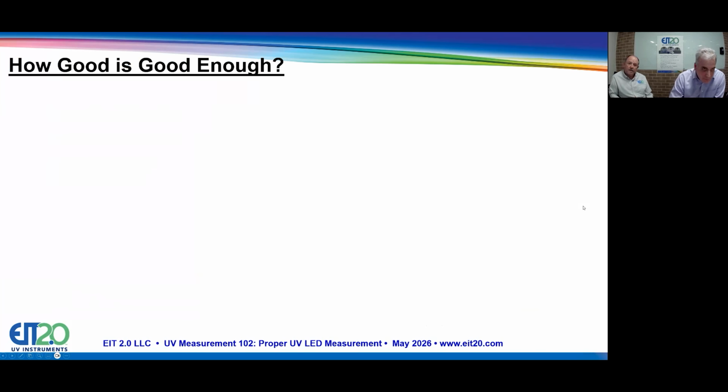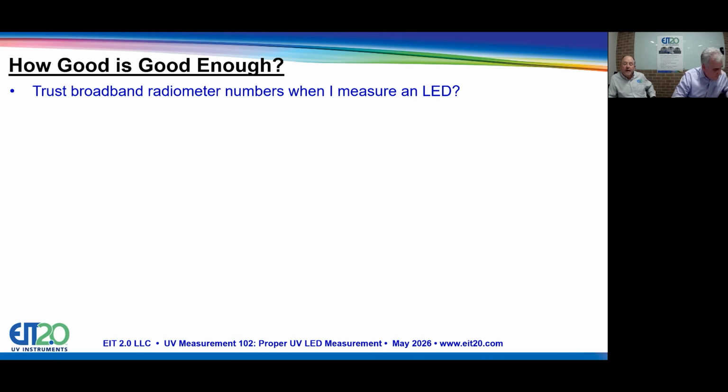So, Jim, enough of the techno talk. Why are we here again? What we want to talk about is how good is good enough. And this is a question that you really have to answer for yourself. We do have customers that use radiometers that are optimized for mercury to measure LEDs. Sometimes they have success with those. In many cases, they get numbers that can lead them astray or lead them down a rabbit hole that makes communication within their supply chain or within their company very difficult.